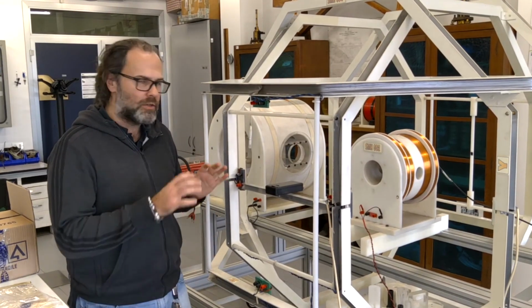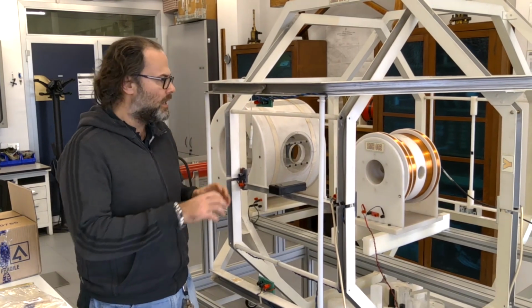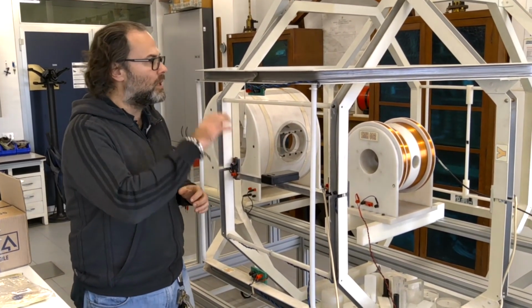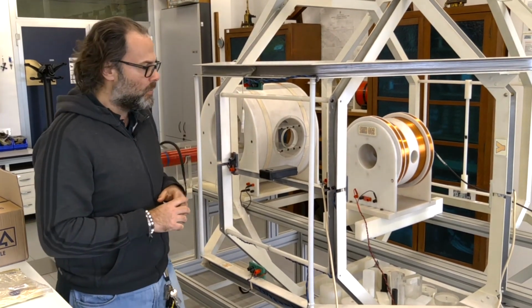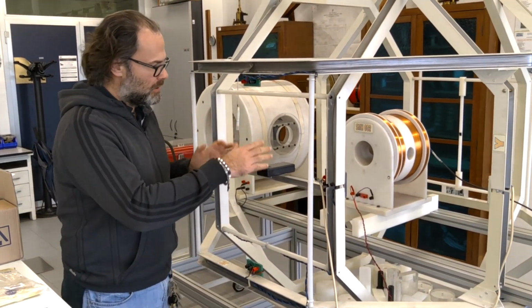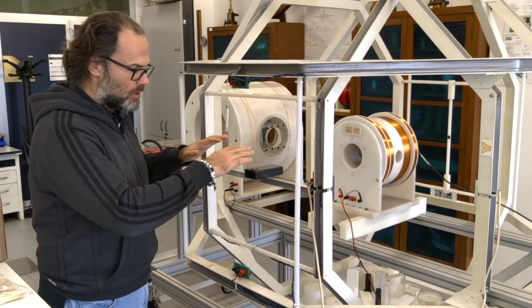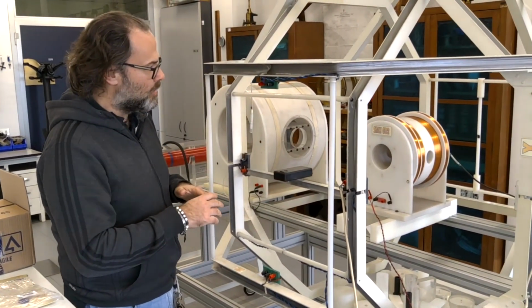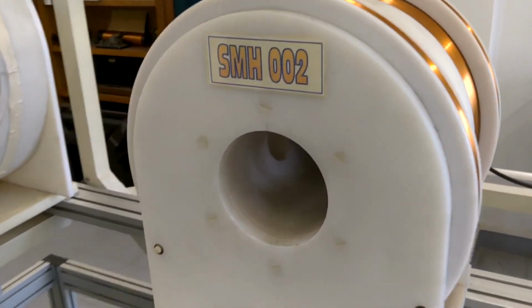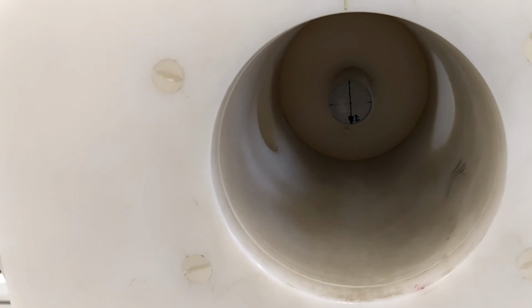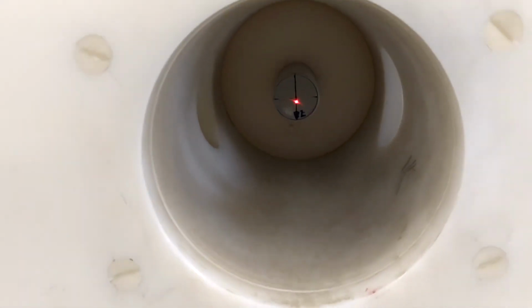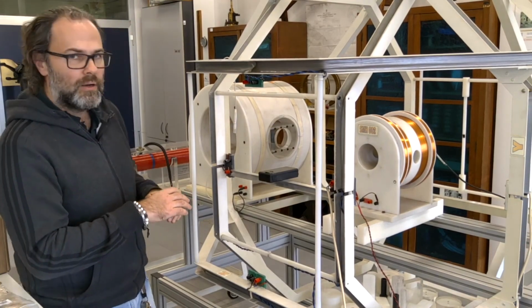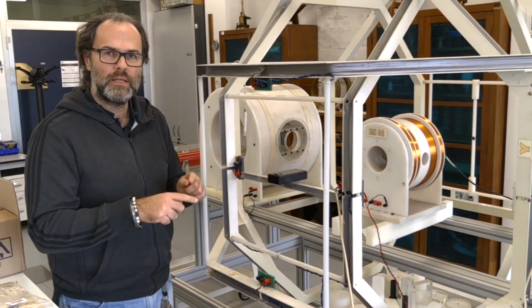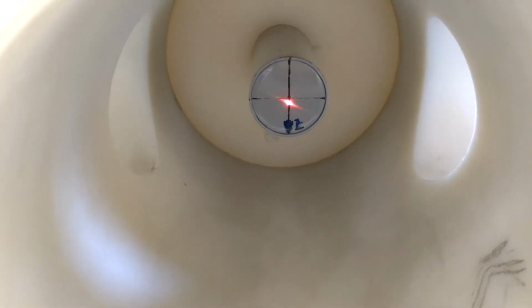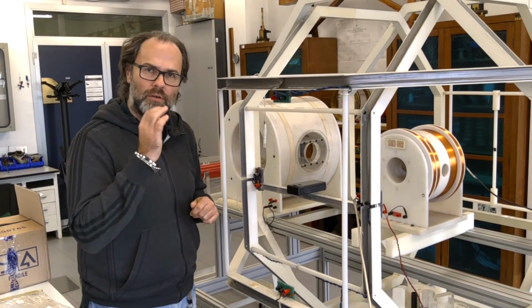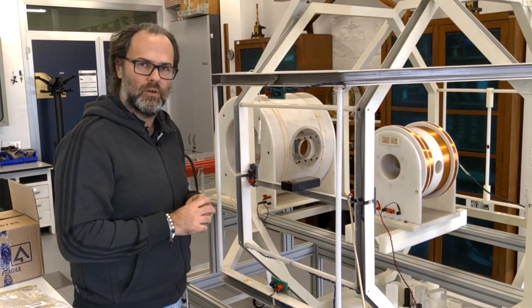In order to ensure the correct positioning of the Flux-Gate sensor in the center of the transfer coils and of the compensating Helmholtz coils, we have a laser that has been positioned once and for all in the correct place and whose spot can be used to identify the correct positioning of the Flux-Gate. So if we switch on the laser and give it time to accommodate for the vibrations, we can check that the laser spot is in the middle of the cross that we have painted on the Flux-Gate, and that ensures that the position of the sensor is in the middle of the volume of the coils.